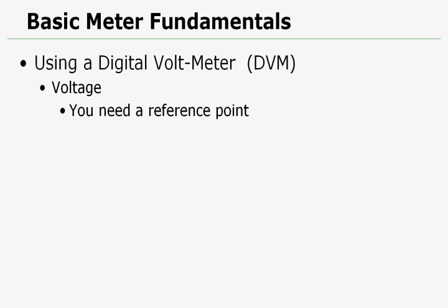You always need a reference point. In our examples, and for just about everything we do in irrigation control for voltage readings, we need an earth ground reference point. That's this little symbol. Put your meter on it, it should have zero volts AC.